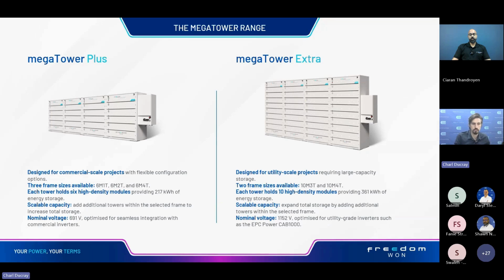The main difference is that the megaTower Plus battery module stacks add up to 217 kilowatt hours of energy storage capacity, with a nominal voltage of 691 volts. That comes into play when determining what inverter to pair with—691 volts is typically the requirement of a commercial inverter.